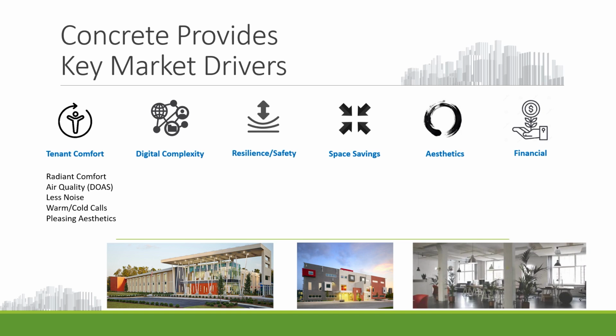This system works almost entirely throughout the year with 100% natural outdoor air flowing into the building. They call these systems dedicated outdoor air systems, and integrated ventilation design throughout the year uses outdoor fresh air to condition the indoor spaces. And this is due to the fact that the heating and cooling energy can be stored in the concrete systems, the thermal cap. When outside air is brought through the ducting that goes through the concrete floors, the air coming into the space is at a temperature that is ideal for the set point that you have set in the building.